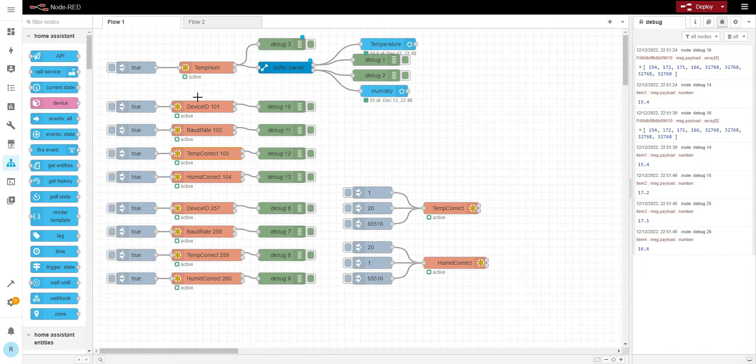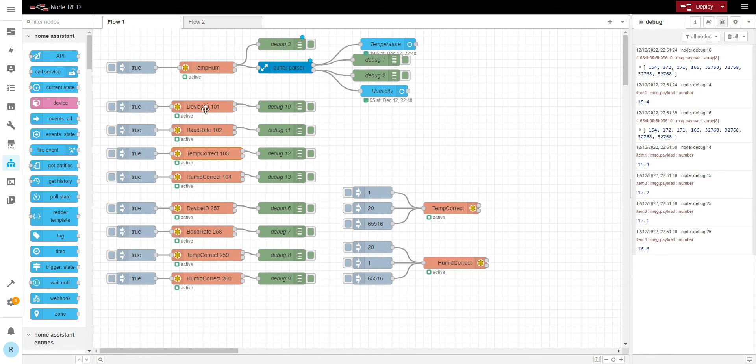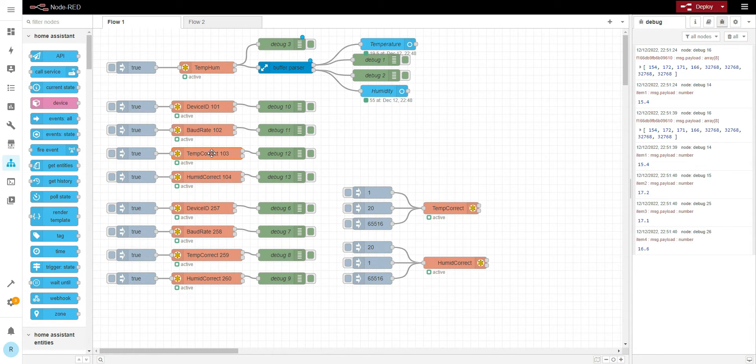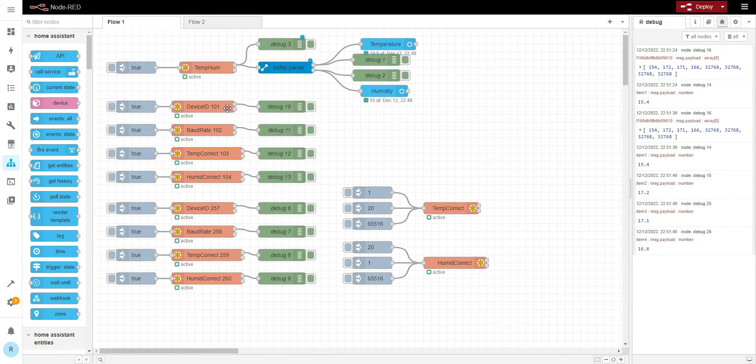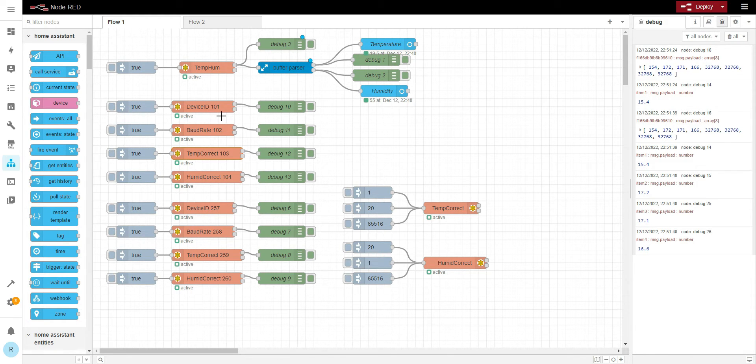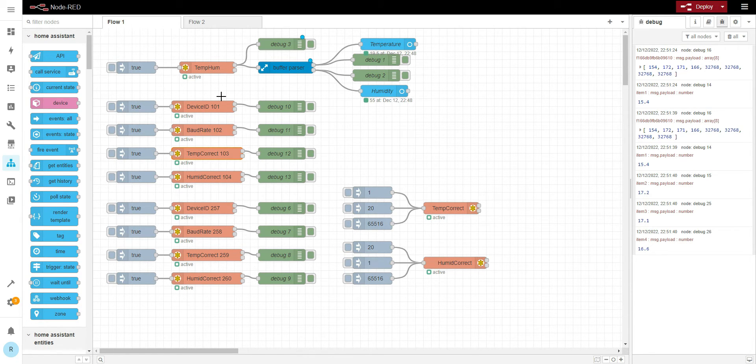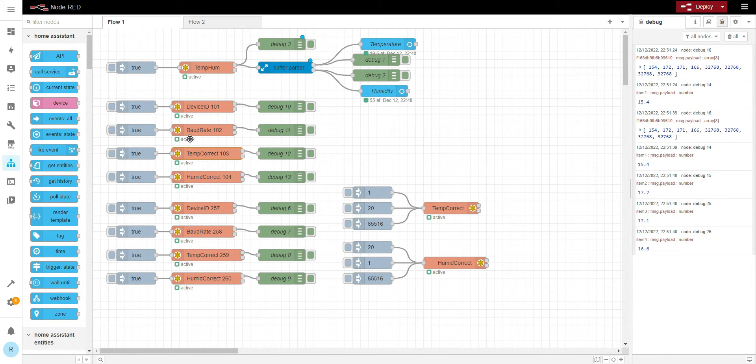Before you restart the device, you will be able to do everything. So imagine you try to find the correct register for temperature correction and by mistake you force one of the registers, which is the device ID register, with some odd number. And then you forgot about it, you switch it off. Then when you come back next day, turn it back on, you can't connect to it. And then you try to remember which registers you were presetting. I hope you understand what I'm trying to say.